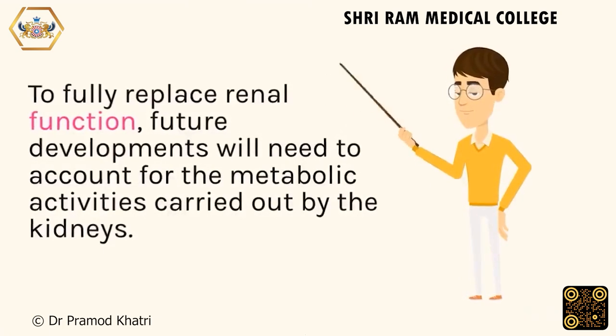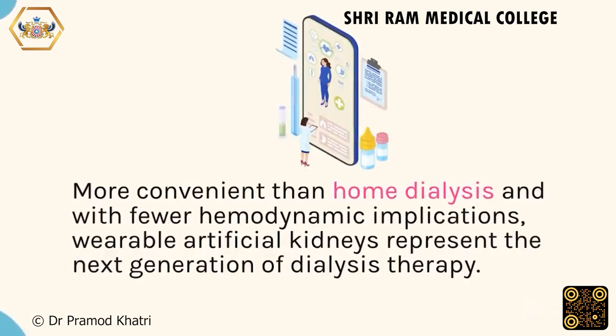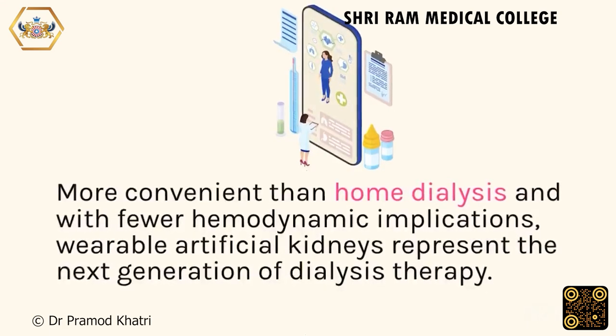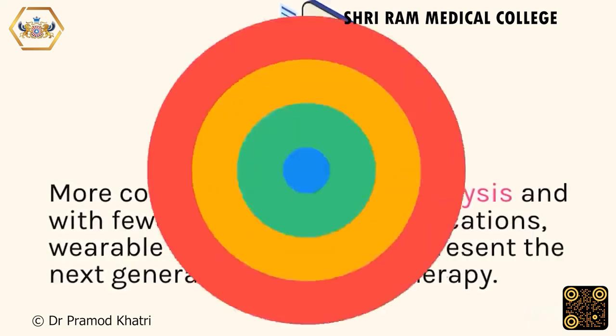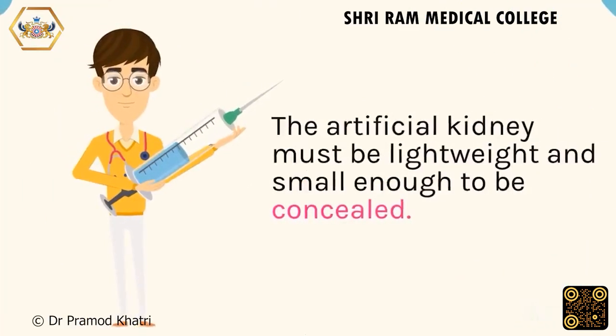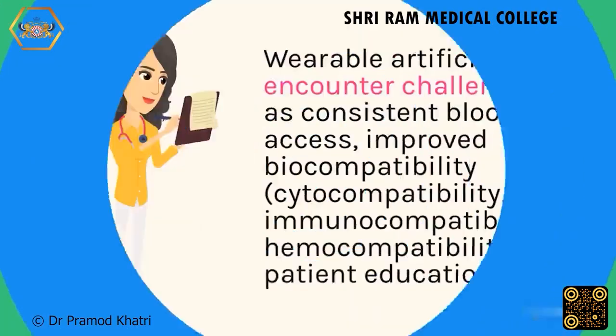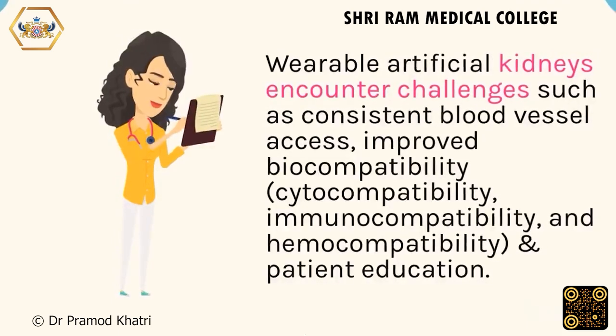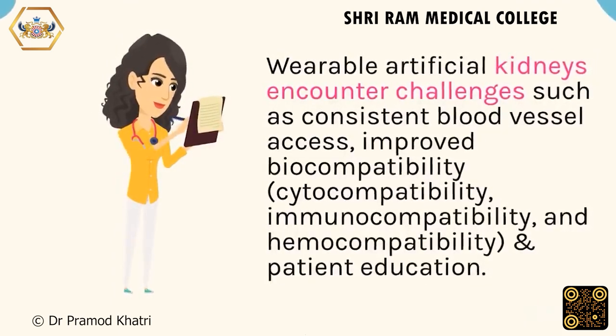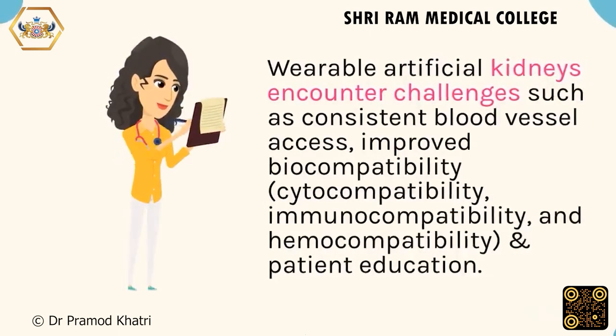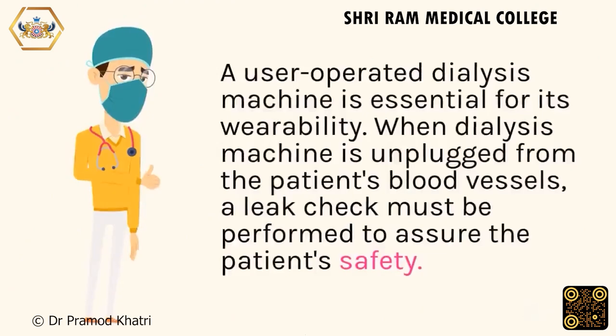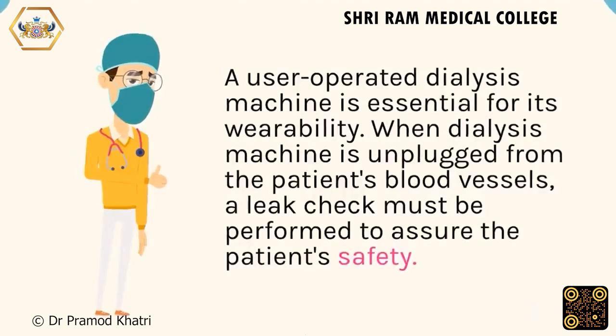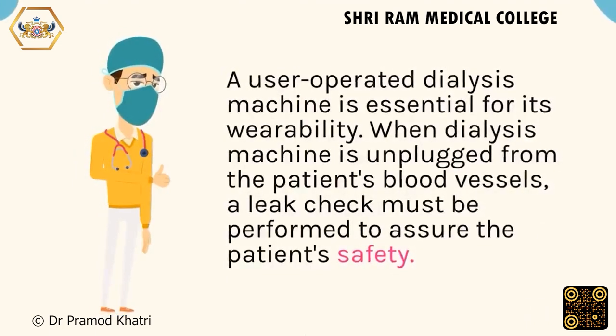More convenient than home dialysis and with fewer hemodynamic implications, wearable artificial kidneys represent the next generation of dialysis therapy. The artificial kidney must be lightweight and small enough to be concealed. Wearable artificial kidneys encounter challenges such as consistent blood vessel access, improved biocompatibility, cytocompatibility, immunocompatibility, and patient education. A user-operated dialysis machine is essential for wearability; when the machine is unplugged from the patient's blood vessels, a leak check must be performed to assure patient safety.